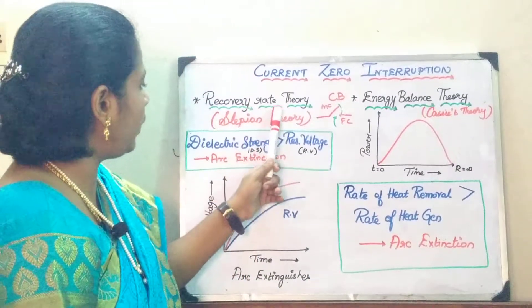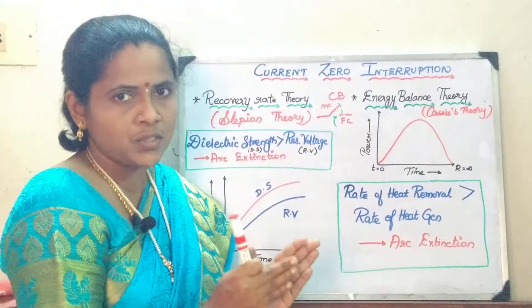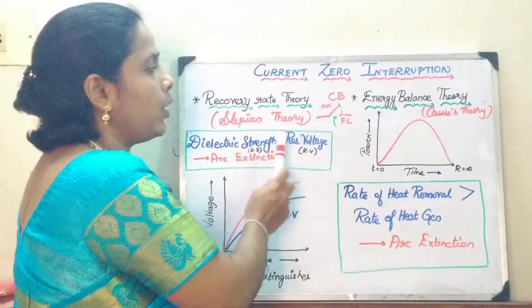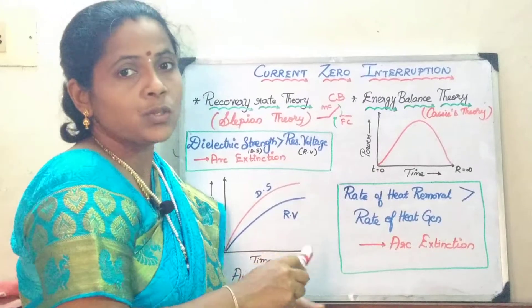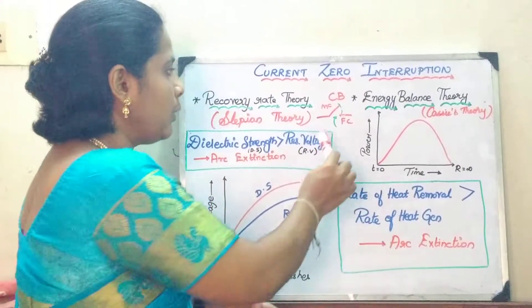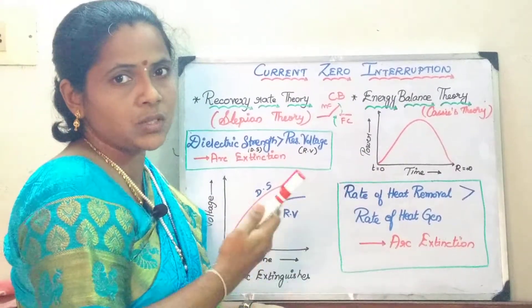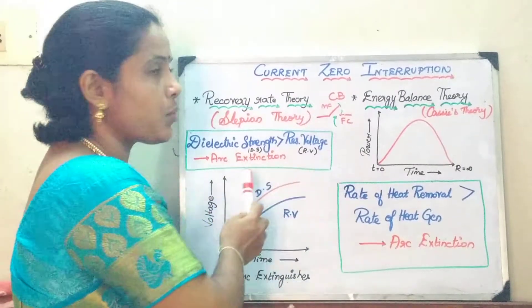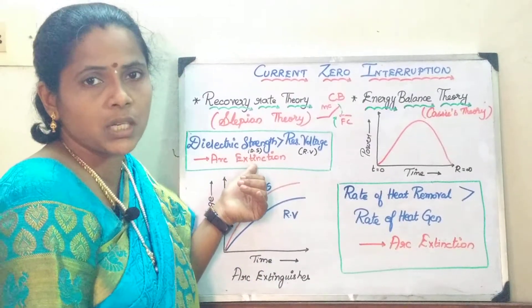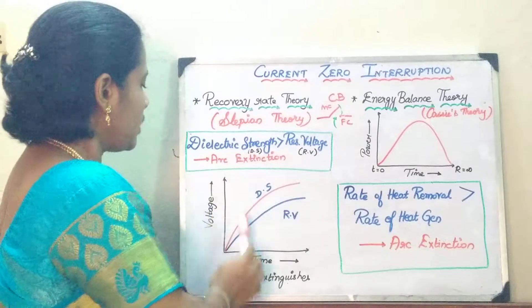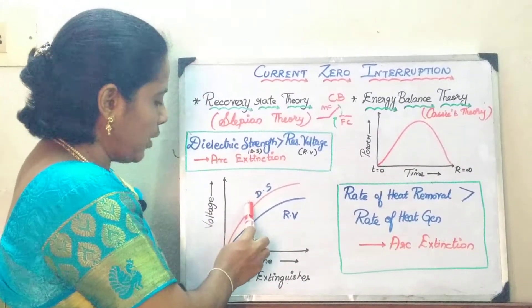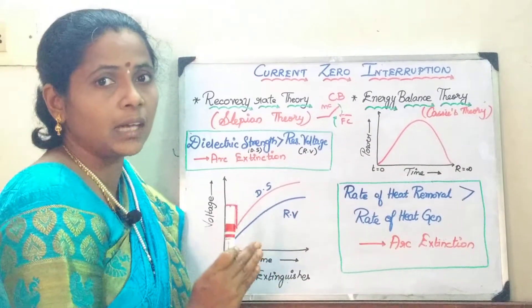When we say recovery rate theory, it means that if the dielectric strength — whatever dielectric strength you are providing — is going to be greater than the restriking voltage, the arc will get extinguished. If you are not going to give any arc quenching medium, it will restrike again. But if you give the arc quenching medium — either oil, SF6, or air — whenever the dielectric strength is greater than the restriking voltage, it results in extinguishing the arc. This graph shows the arc extinguishing phenomenon: where dielectric strength is more than the recovery voltage, the arc will get extinguished.